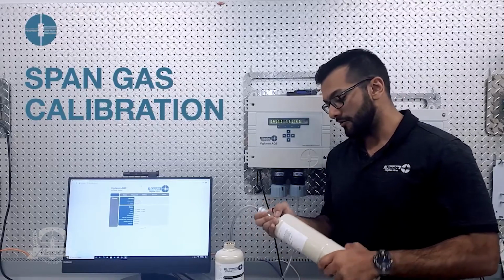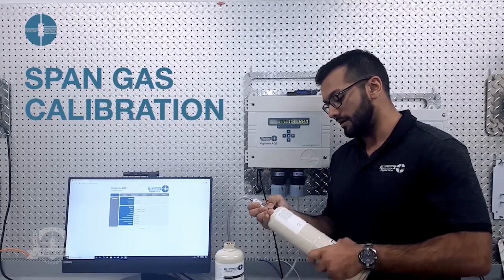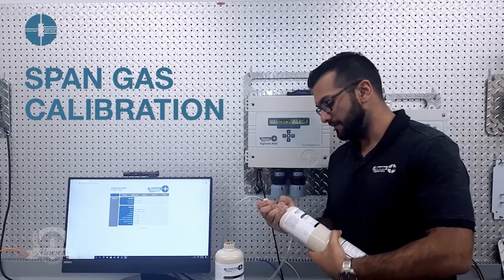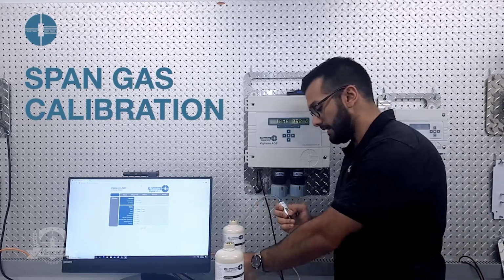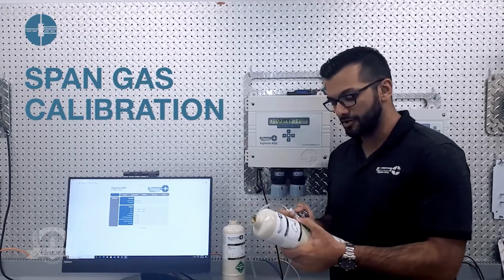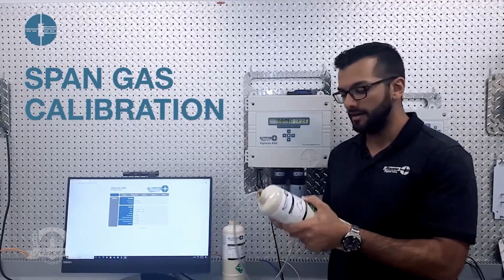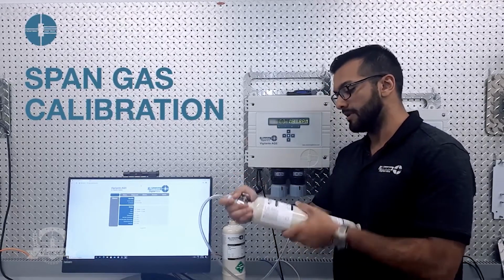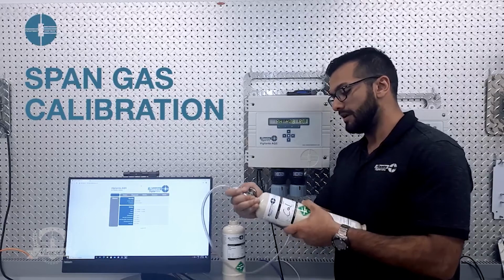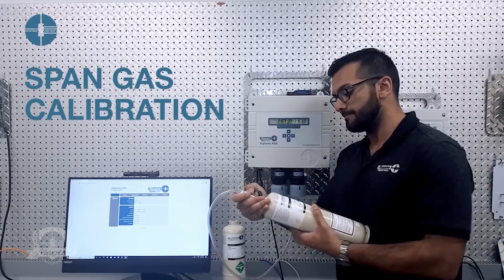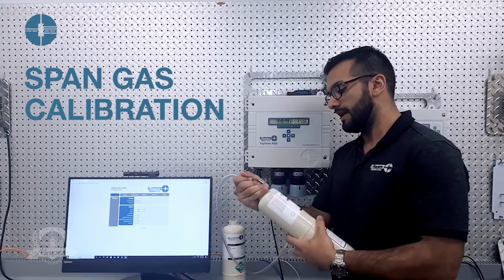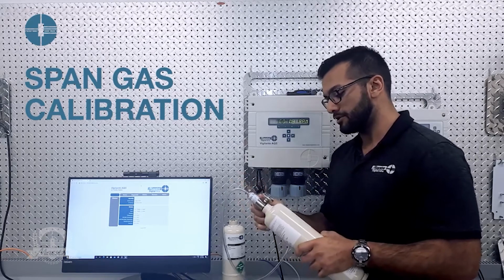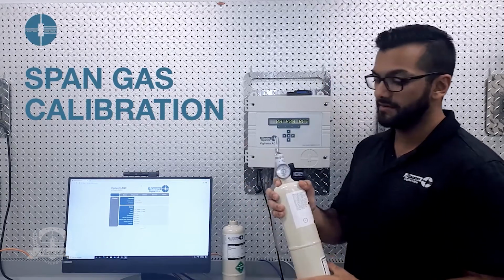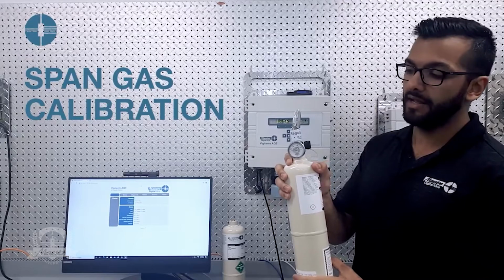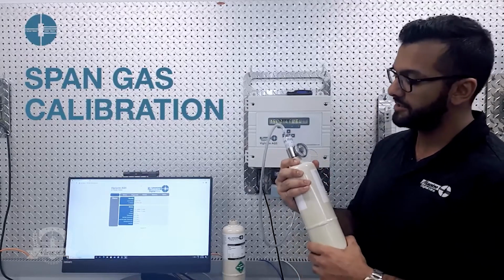So for that, you're going to remove the regulator from the zero gas bottle itself. And again, the best thing is to make sure that your calibration gas is still valid. This one is, and you'll plug the regulator onto the span gas bottle. And again, it's always important to check, make sure that you actually have gas in the bottle itself. So here you can see that the regulator does show that we have plenty of gas here.